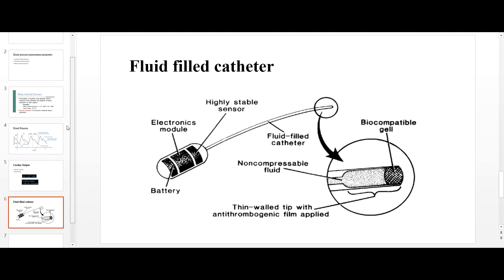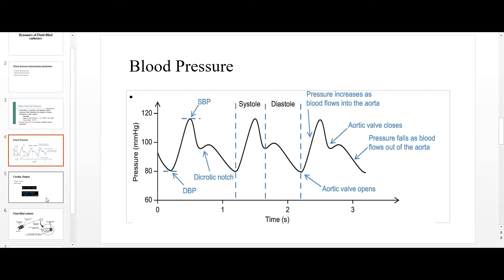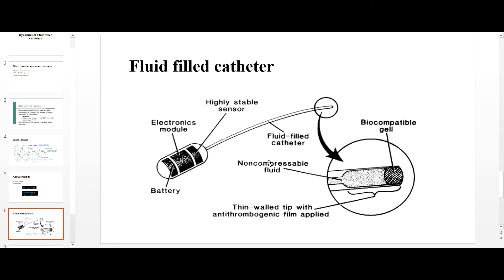In summary, the dynamics of fluid-filled catheters refers to the variation of systolic and diastolic blood pressure with respect to time, as measured by this catheter. The fluid-filled catheter has a biocompatible gel tip at one end to prevent blood clotting, and a transducer at the other end to measure the reflected pressure wave transmitted through the fluid. Pressure waveforms with respect to time are thereby continuously measured. Thank you.